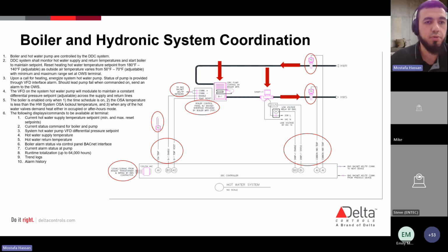So your boiler and hot water pump are controlled by the DDC system. There is your boiler, and there is your hot water pump. Okay, there's a singular hot water pump here. I don't see a lead lag need, but we're working along with the sequence of operations. It also mentions that the boiler control panel comes with a BACnet interface from the boiler manufacturer. So I like this note a lot. Again, it makes it very easy.